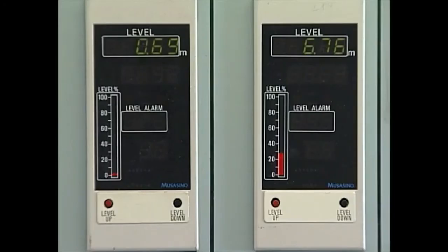As the water level drops further to approach the tank bottom, now exercise precautions against air drawing. Watch the gauge carefully and readily respond to the risk of air drawing.